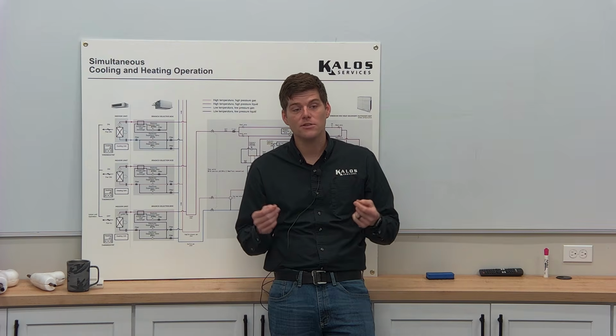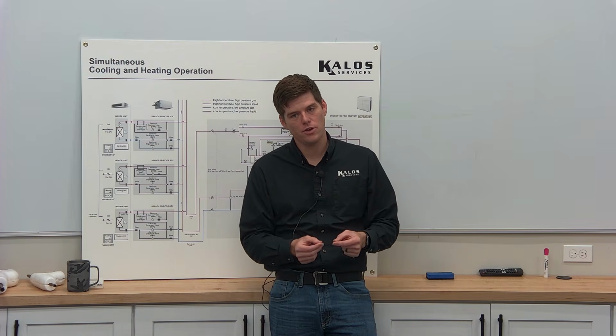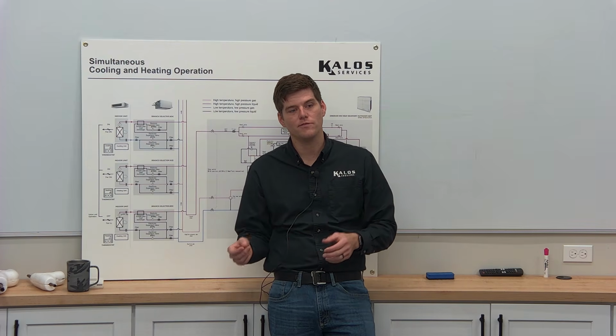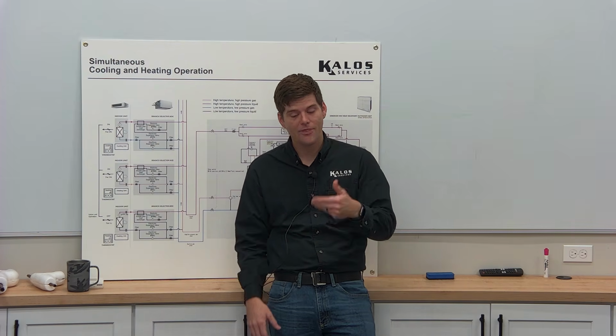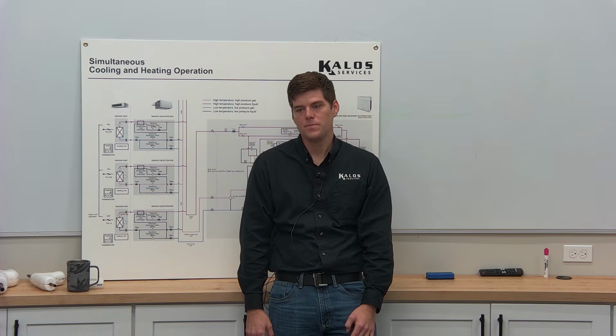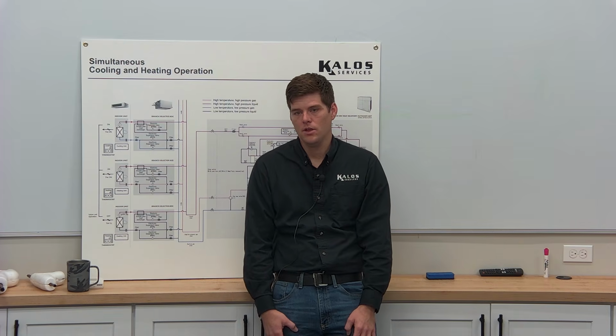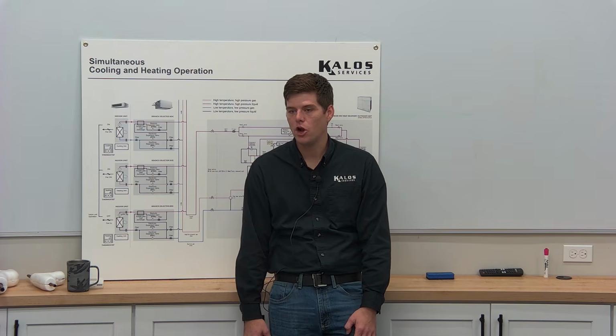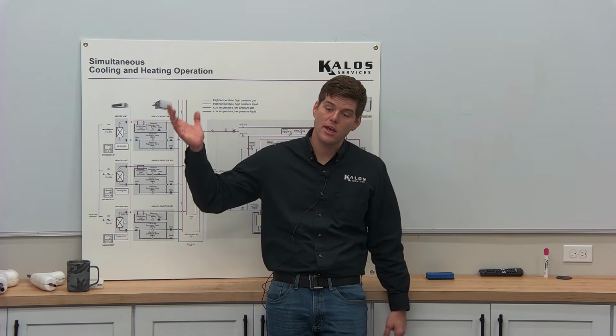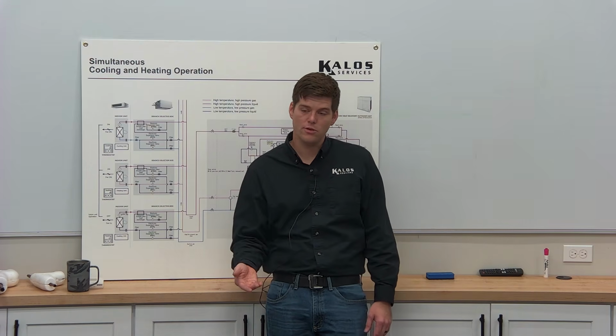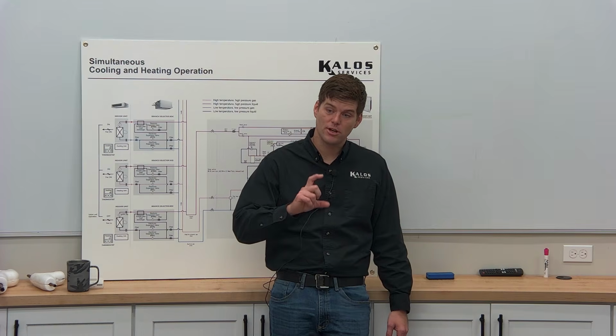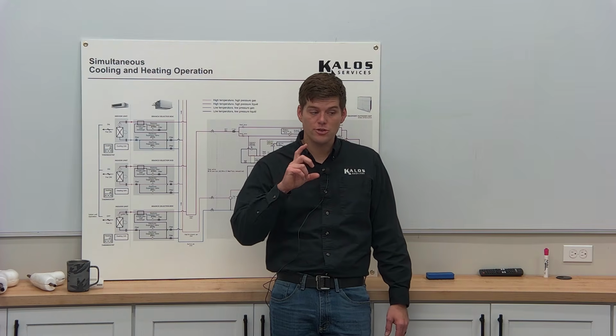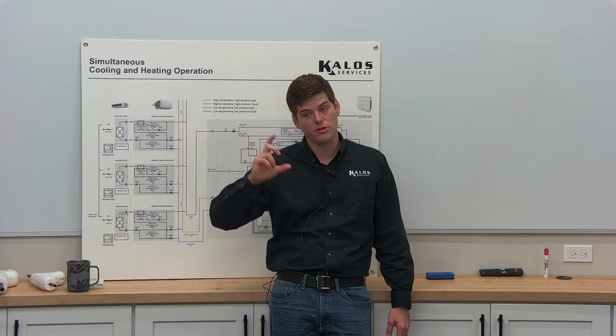The metering devices for these systems are always in the indoor unit. There is always going to be an electronic expansion valve metering flow at the indoor unit. It could also act as a solenoid too, though, right? Well, sure, it could close, right, and it could open. Other manufacturers like Daikin, they don't use solenoid valves. They use electronic expansion valves. And those are usually 0 to 3,000 pulses or 0 to 6,000 pulses.